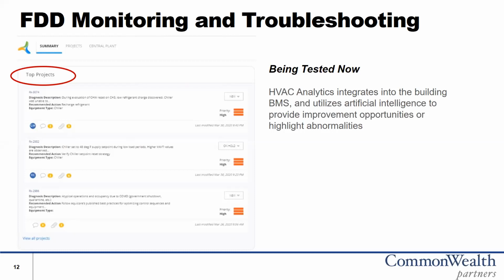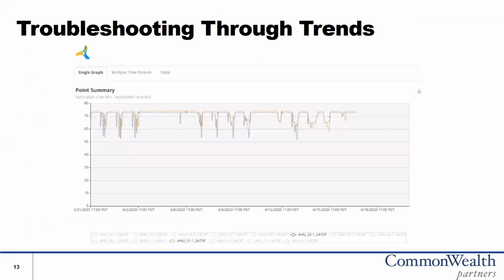One example of a project, on the next slide: you can easily hone in on comparing individual pieces of equipment. You can pick two identical air handlers and run their trends side by side. Here we noticed one air handler, identical to the other, routinely running a much lower discharge temperature. So what's driving that?